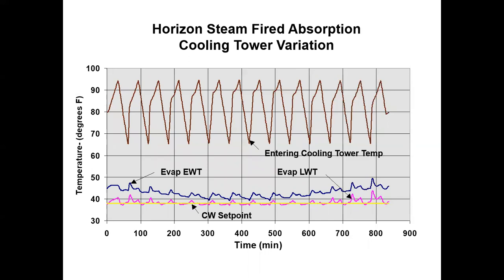Oh, and this is cycling the cooling tower water. And they're doing their best to screw this guy up, from about 95 down to about 65. And you see the pattern of entering cooling tower temperature. Yeah, cooling tower variation. So you see how the evaporator responds. This is entering water temperature of the evaporator. This is leaving water temperature from the evaporator. I mean, that's pretty darn good. The yellow line is the set point. So when you're monkeying with it to that extent, I'd say they were probably pretty happy with that result.